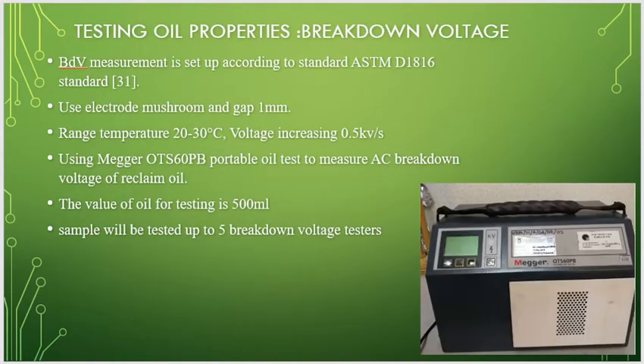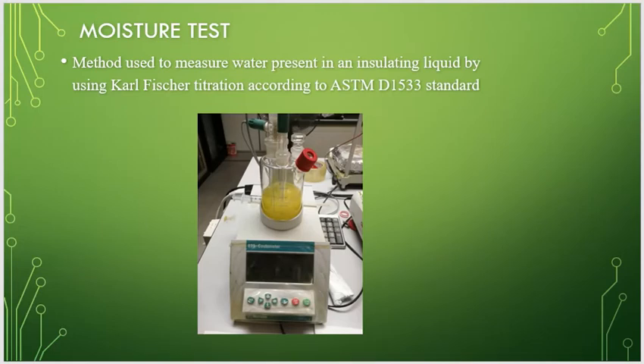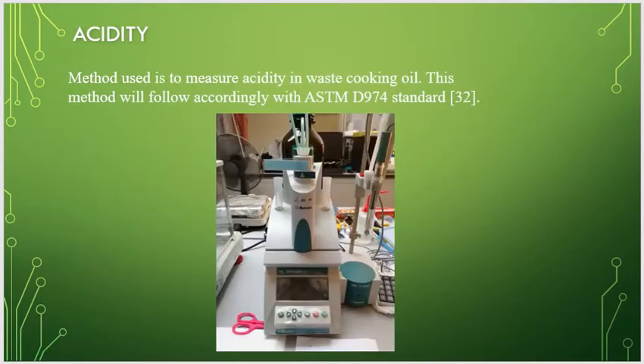Then testing oil property breakdown. We use a Megger, and the temperature range for the oil is 20 to 30 degrees Celsius. And the volume of oil for testing is 500 milliliters. Then for the moisture test, we use coulometric titration, and the oil sample will be calibrated before testing moisture.